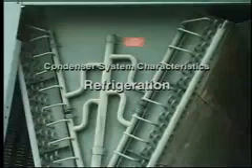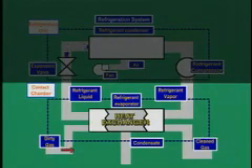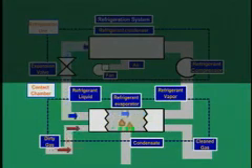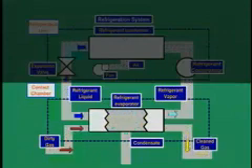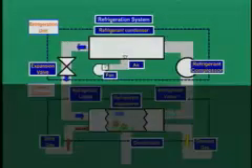Refrigeration systems use compressed coolants and operate at temperatures as low as minus 150 degrees Fahrenheit. The most common coolants use CFCs, although this is changing in response to the Clean Air Act amendments of 1990. The refrigerated liquid, flowing through tubes in a shell and tube heat exchanger, absorbs heat from the gas stream flowing on the shell side, reducing the gas stream temperature and causing the contaminant to condense. The absorbed heat causes the refrigerant liquid to change to a vapor.